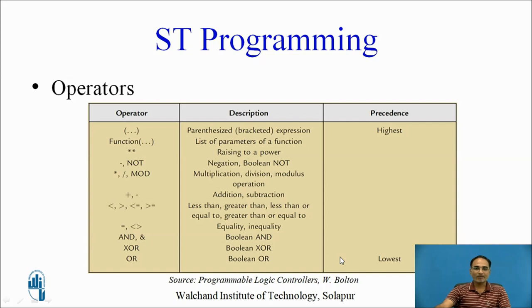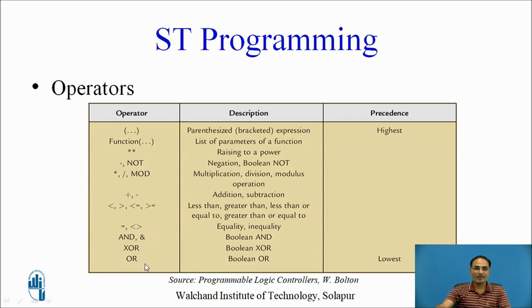Before going into the details of structured text programming, let us go through the operators. These operators are listed from highest to lowest precedence. Brackets have the highest precedence, while the OR operator has the lowest. The order is: brackets, function invocation, exponentiation (power), NOT, multiplication/division/MOD, addition/subtraction, comparison operators (less than, greater than, less than or equal to, greater than or equal to), equality/inequality, Boolean AND, Boolean XOR, and Boolean OR.